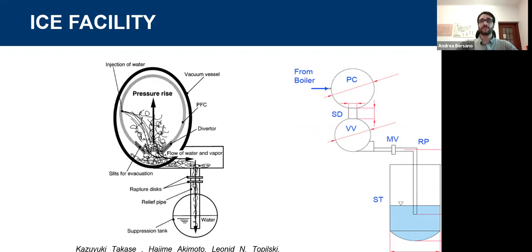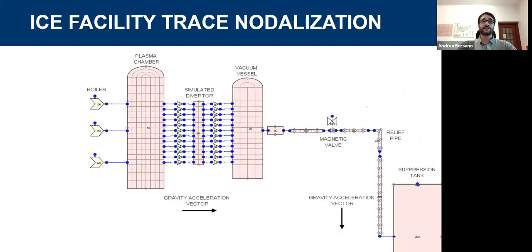In particular, the pressure suppression system is this suppression tank where we have the discharge of the water from the vacuum vessel. This is a representation of the nodalization that we developed through SNAP for the TRACE code. And this is a quite complex nodalization because in this facility, we have multidimensional flow. So we have the injection of water horizontally, and then the flowing of water from the plasma chamber to the vacuum vessel vertically. So we adopted a three-dimensional nodalization.